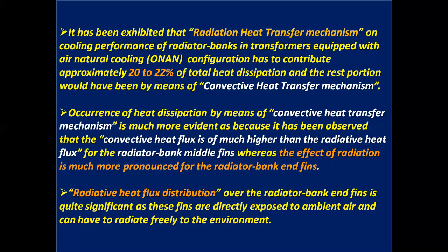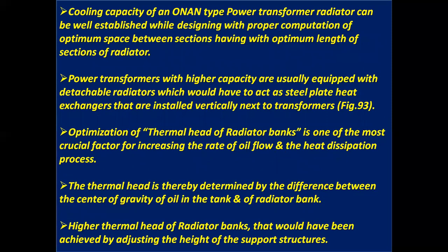Radiative heat flux distribution over the radiator bank end fins is quite significant, as these fins are directly exposed to ambient air and can radiate freely to the environment. The cooling capacity of an ONAN type power transformer radiator can be well established while designing, with proper computation of the optimum space between sections and the optimum length of sections of the radiator. Power transformers with higher capacity are usually equipped with detachable radiators, which act as steel plate heat exchangers installed vertically next to transformers, as in figure 93.